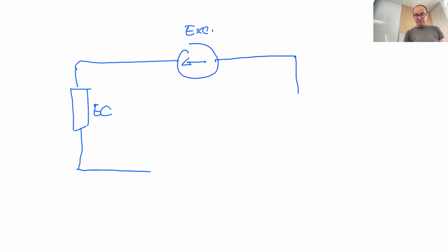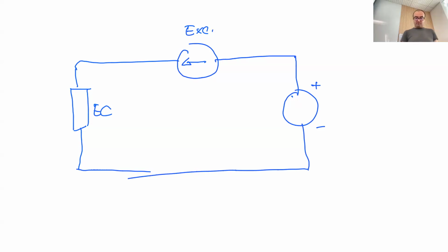And then there is a main power supply that is installed already here. So our excitation, so this power supply, we put it in constant voltage mode. It just follows, and because in constant voltage mode it has high bandwidth, it will not influence the impedance of the electrolyte. In this unit here, we have pre-programmed excitation signals.